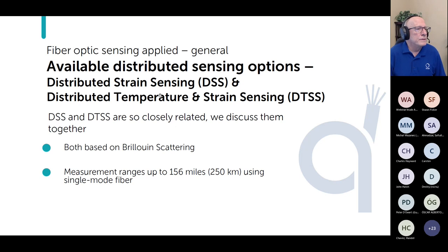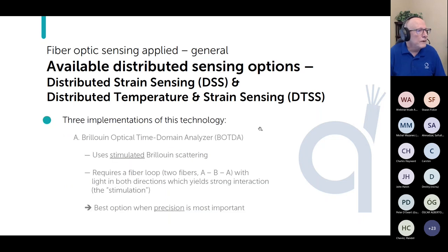So next up, distributed strain sensing and distributed temperature and strain sensing. So DSS and DTSS are closely related. And the reason is that both are using Brillouin scattering as the underlying concept of how they operate. You can get very long distances using single mode fiber for either of these. There are currently three implementations of this technology. First up is Brillouin Optical Time Domain Analyzer, so BOTDA. In this case, you're actually stimulating that Brillouin scattering effect. And you do that by making a fiber loop. So you've got two fibers.